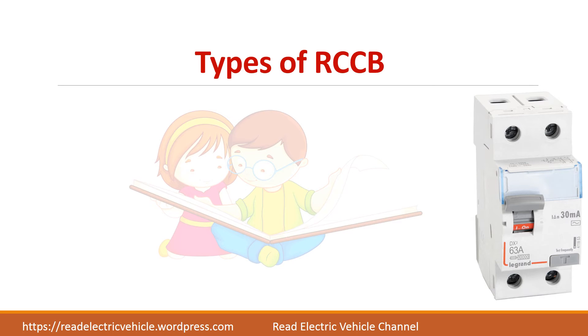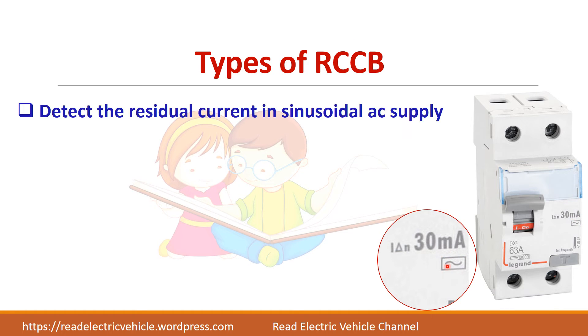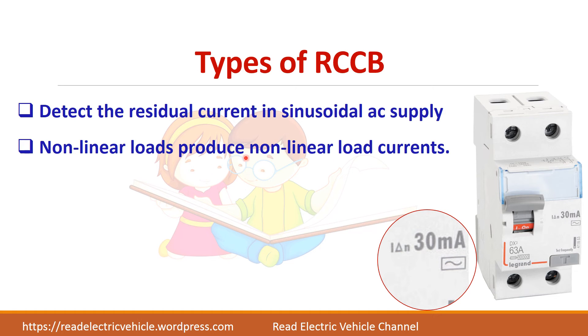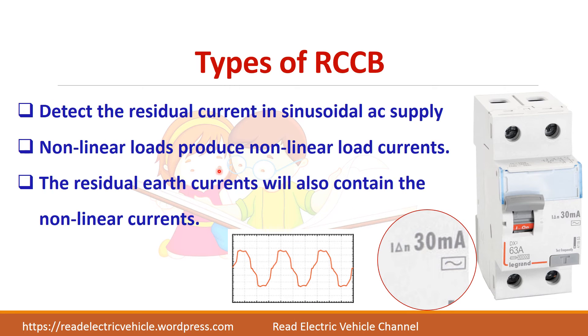Next, we will see the different types of RCCB. In one model, a sine waveform is shown in a box, which represents that this particular RCCB can only detect the residual current if it is sinusoidal in shape. But today, most of our loads are non-linear because we are using power electronics everywhere, which draws only non-linear current. In such cases, the residual current will also be non-linear and this type of RCCB will not be able to detect non-linear currents.